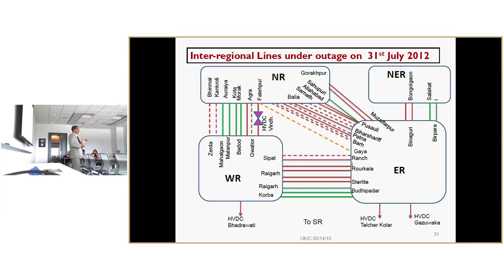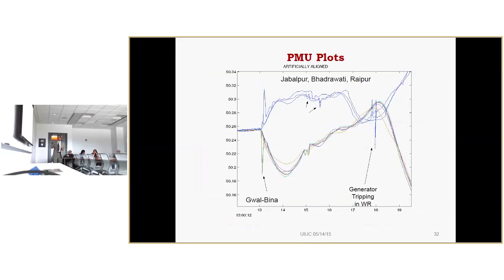This affected 670 million people. But restoration was relatively faster. It was 7 hours compared to 14 hours on the first day. These are the PMU plots. In fact, at one point, it was getting synchronized. But some generator tripped at this moment in the western region, and then again it separated. It could have remained synchronized. So what we conclude is that we could not assess the dynamic situation. We could not take any corrective action.